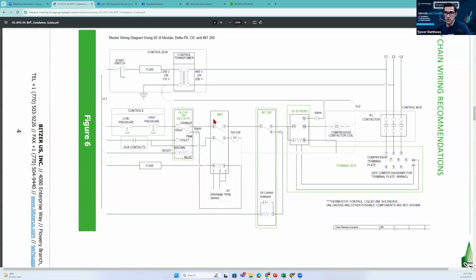Then you have your refrigerant injection module. This is the BMT for this design. And then you've got the INT. This is your motor overload. And then this is your INT 280 oil control solenoid. So this is the oil level control, and this is your motor overload.